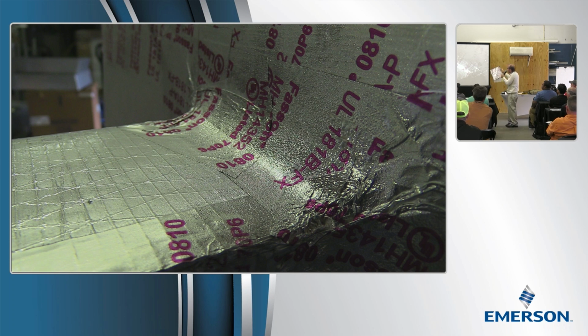A lot of times people will see this and say, well, it's colder around the joint, or there must be insulation missing. No, the only thing going on is that this is the same temperature as that, but the moisture molecules are going deep into this material rather than staying on top. In this case, they're condensing on top. You'll notice that on non-permeable surfaces, it's all on top, and then when you get to something like this, it becomes damp to the touch, but you don't see it sweating.